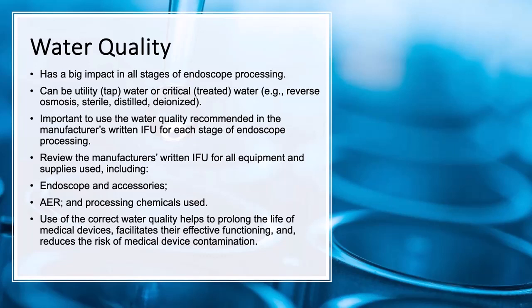Water quality. Oh, we're hearing so much about this now, and it does have a big impact on all stages of endoscope processing. You can have utility or tap water or critical treated water, such as reverse osmosis, sterile, distilled, or deionized water. You must follow the water quality recommended in the manufacturer's instruction for each stage of endoscope processing. Your water for cleaning may be different from the water in the initial rinse, which could be different from the water quality in the final rinse.